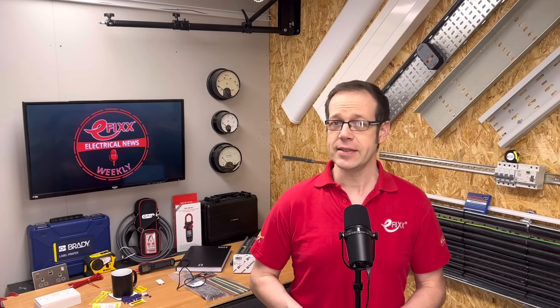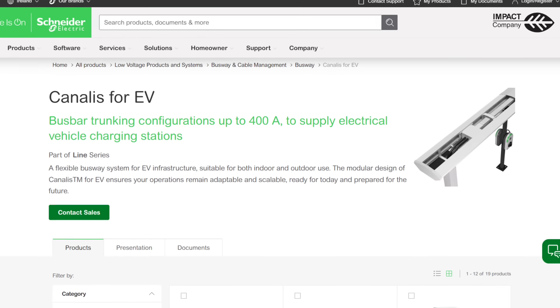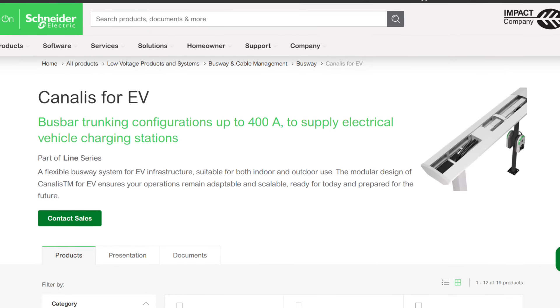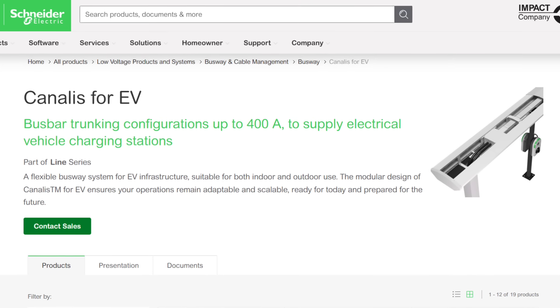Schneider Electric has unveiled a busbar trunking product specially designed to supply electric vehicle charging stations. The Canalis for EV system allows for configurations up to 400 amps and is suitable for outdoor use. It's a modular plug-and-play platform that reduces the amount of civils work that needs to be done. Tap-off points along the busbar connect to individual chargers, and there's even an option to provide lighting, as charging stations can often be dark and unwelcoming.